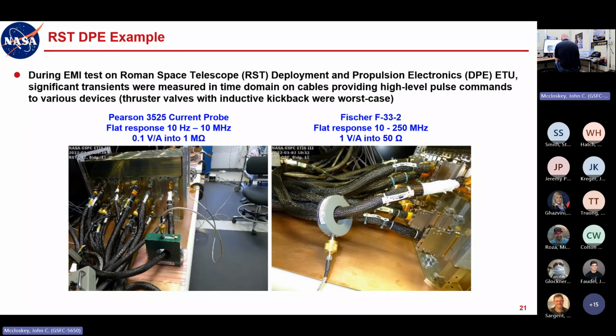The one on the left is the Pearson 3525. It has a flat response from 10 hertz out to 10 megahertz. The transfer impedance is 0.1 ohms, or volts per amp, into 1 megohm, or it's 50 millivolts per amp into 50 ohms. But it's nice to go into 1 megohm because that makes the conversion very handy. It's just a factor of 10, right?